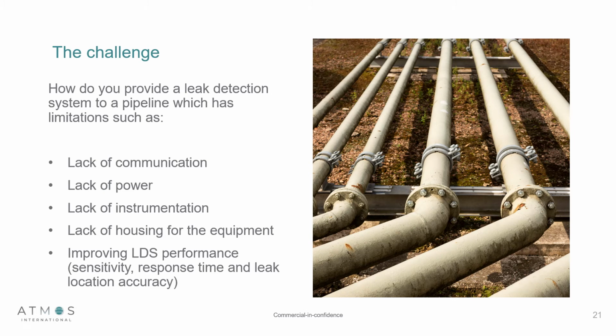As well as this, we have the issue with the negative pressure wave that has challenges with transient conditions, and it also has challenges with reliability, as it can in some scenarios generate false positives. So what has Atmos done? Well, we've looked at the challenges that we're facing on pipelines, and we're facing with providing reliable, sensitive and accurate leak detection systems. We come across the following problems: lack of communication on the pipeline, lack of power, lack of instrumentation, lack of housing for our equipment, and also we have the issue of trying to improve leak detection performance on these pipelines.